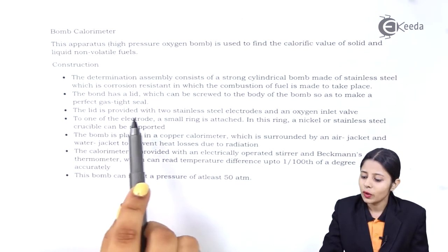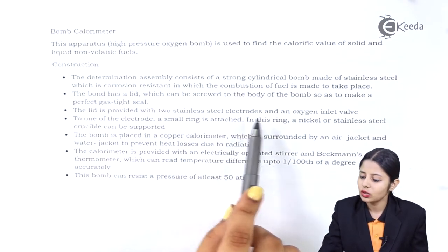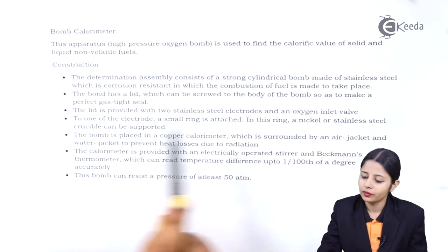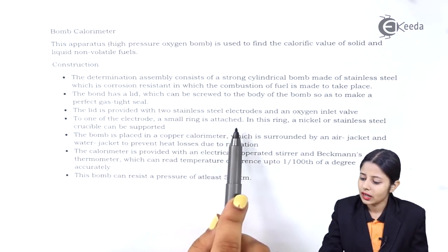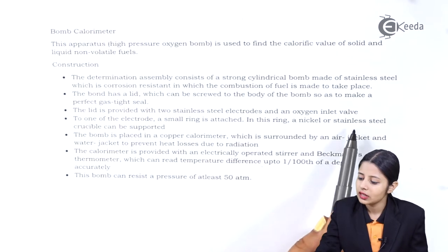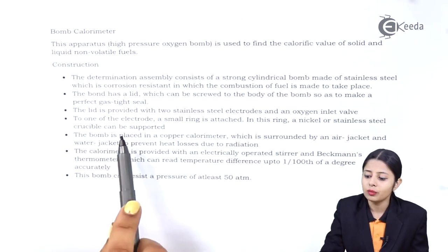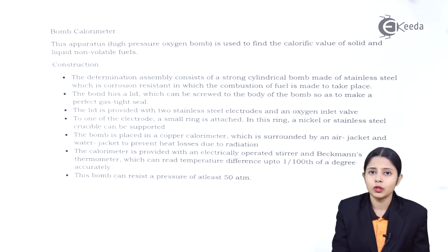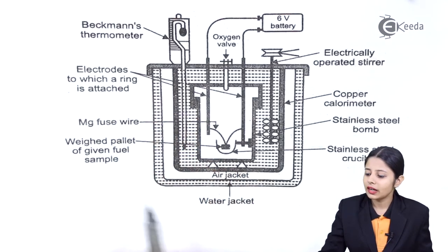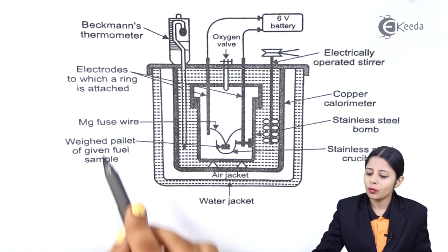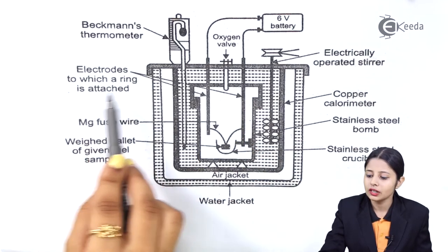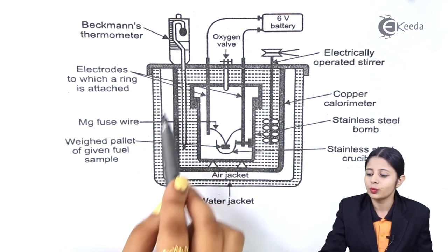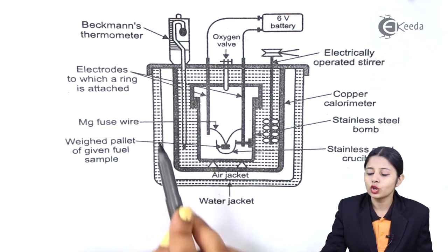The lid is provided with two stainless steel electrodes and an oxygen inlet valve. To one of the electrodes, a small ring is attached, and in this ring a nickel or stainless steel crucible can be supported. Now let me show the diagram of the bomb calorimeter. This electrode to which a ring is attached can support a small crucible.